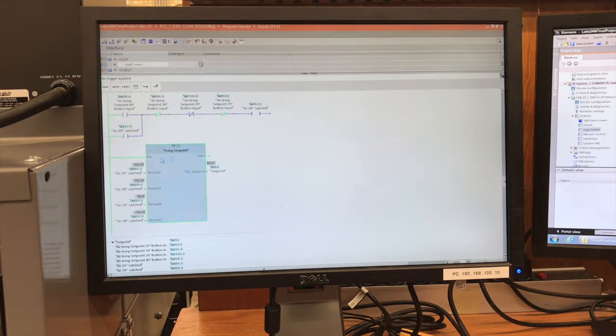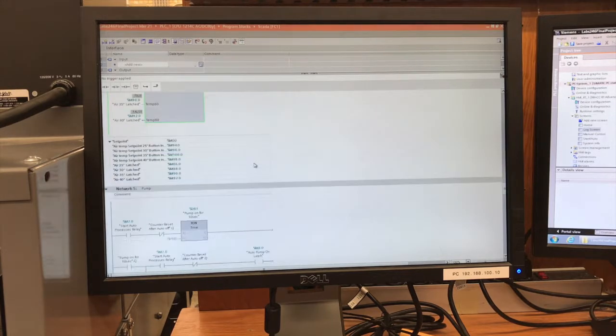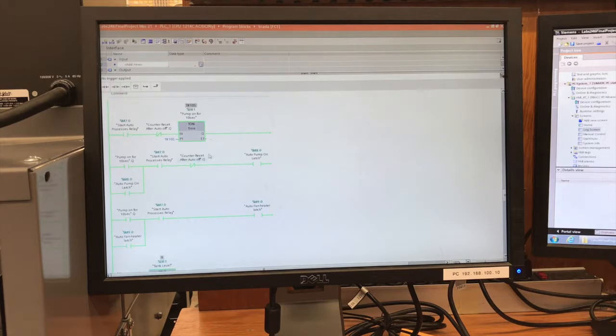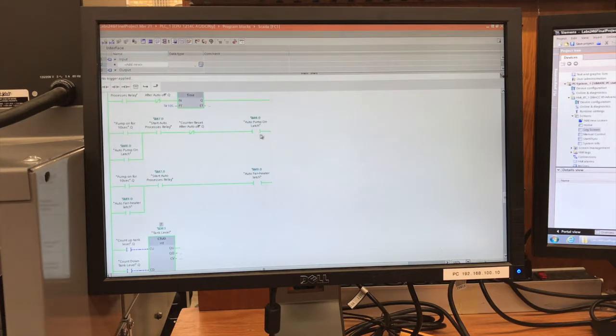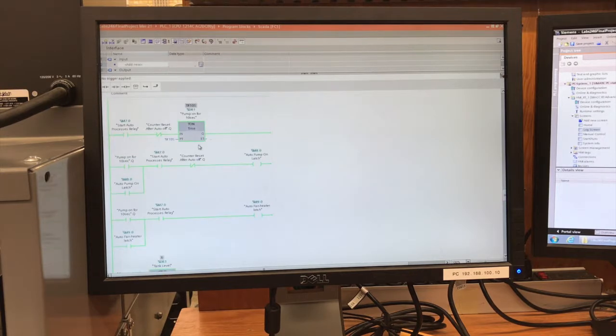So down here is our error set point selection. We created a block that will take in values from our HMI, and we'll actually scale it accordingly to what we select. So right now 60 is set true, so temperature output is 60. This is the auto processing area. So the top block, the TON, is to turn on the pump for 10 seconds. Once the pump turns on for 10 seconds, it is then turned off. The fan and heater are then turned on to complete the process. This process cycles every 70 seconds.